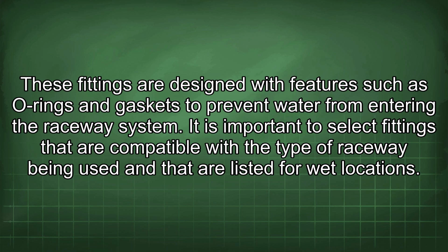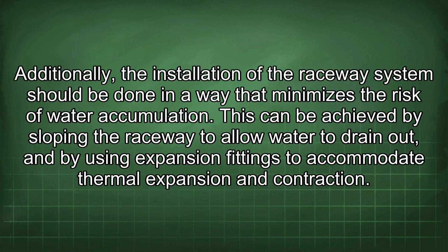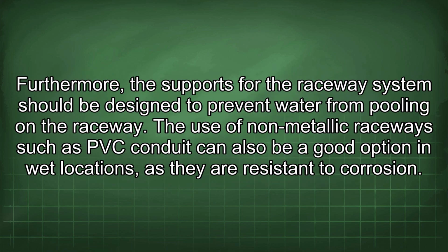It is important to select fittings that are compatible with the type of raceway being used and that are listed for wet locations. Additionally, the installation of the raceway system should be done in a way that minimizes the risk of water accumulation. This can be achieved by sloping the raceway to allow water to drain out, and by using expansion fittings to accommodate thermal expansion and contraction. Furthermore, the supports for the raceway system should be designed to prevent water from pooling on the raceway.